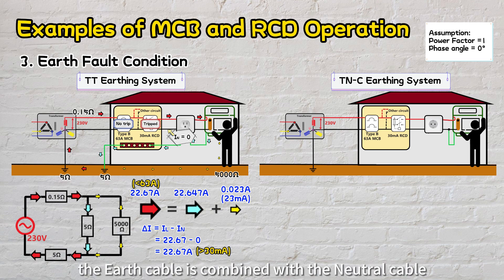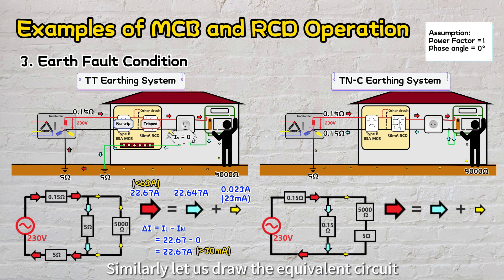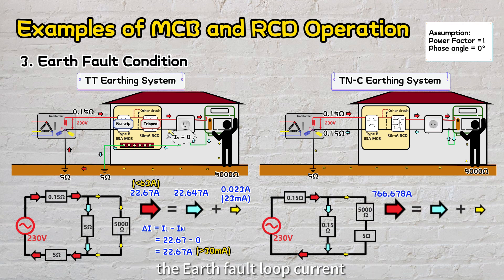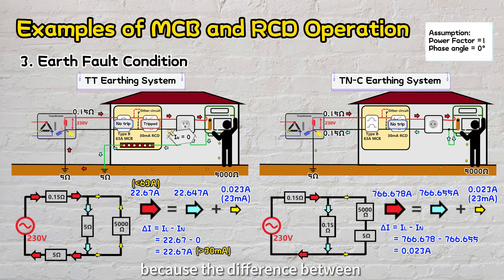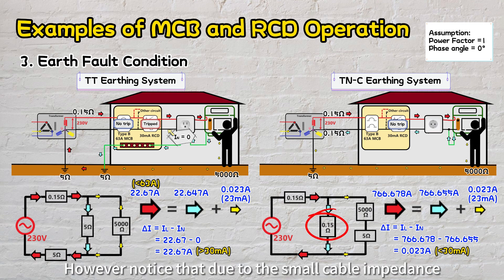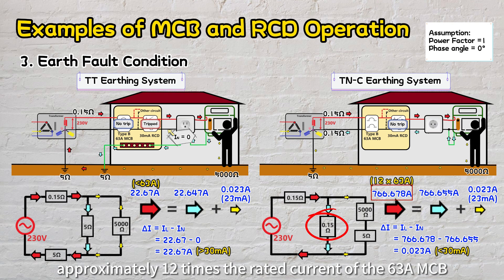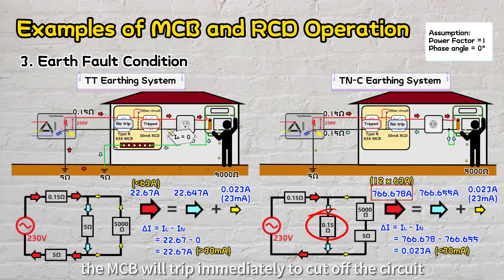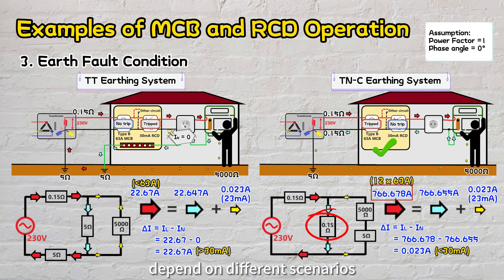In a TNC system, the earth cable is combined with the neutral cable. During an earth fault, the complete loop includes lower cable impedance. Using Ohm's law, the earth fault loop current is calculated as 766.678 amps, with approximately 0.023 amps flowing through the human body and the rest flowing through the combined neutral/earth cable back to the transformer neutral point. In this case, the RCD will not trip because the difference between live and neutral currents is only 23 milliamps, smaller than the 30 milliamps sensitivity threshold. However, due to the small cable impedance, the total earth fault current is approximately 12 times the rated current of the 63 amps MCB, so the MCB will trip immediately to cut off the circuit. We notice that in a TNC system, the MCB trips, but the RCD may or may not trip depending on the scenario.